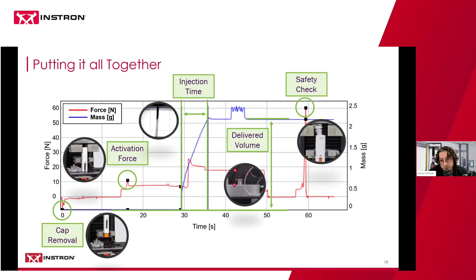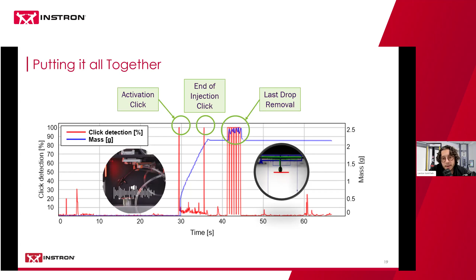And then this is just another graph showing a superposition of the mass and the microphone readings, to show the click detection on the device, and how you can use that as a way to do a quick gut check of the injection time. One characteristic that we get asked about is what is the actual amount of fluid still coming out after that second click? In some cases, there's still fluid coming out of the needle at that point in time, and having all this data, you could easily assess that. And there is some impact on the scale from the last drop, but it's relatively minimal, and that also is picked up by the microphone.